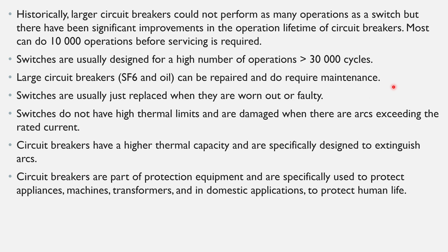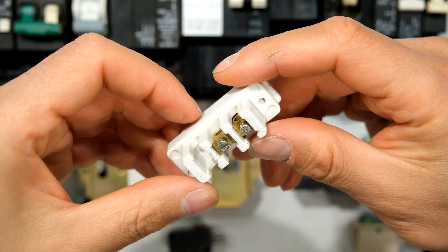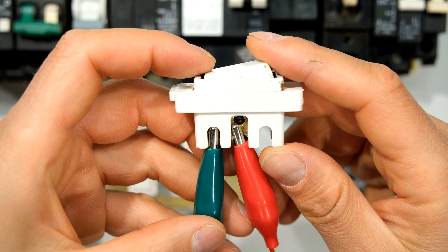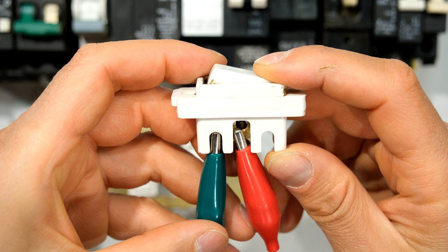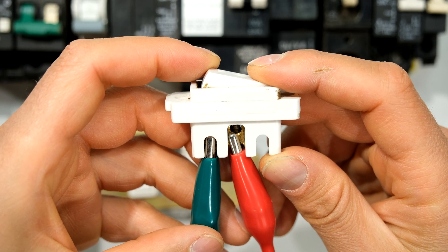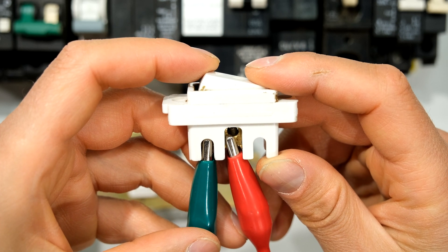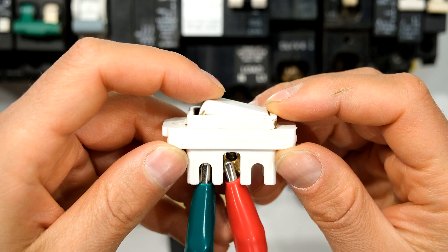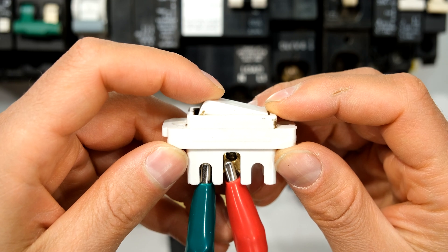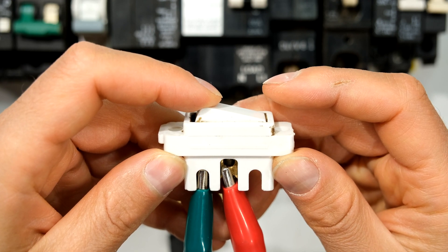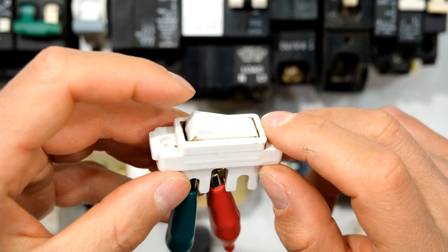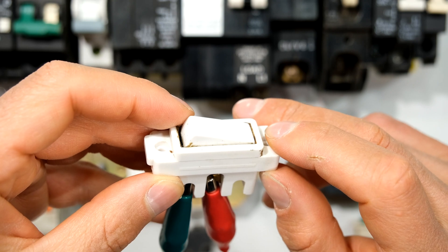Switches do not have high thermal limits and are damaged when there are arcs exceeding the rated current. For example, this switch has a maximum voltage of 250 volts and a maximum current of 16 amps. If the current exceeds 16 amps — say 20 amps — the switch may be damaged. You might find the contacts start to fuse together, and if you operate the switch you might hear it arcing, feel it getting hot, and see it become discolored with carbon buildup.